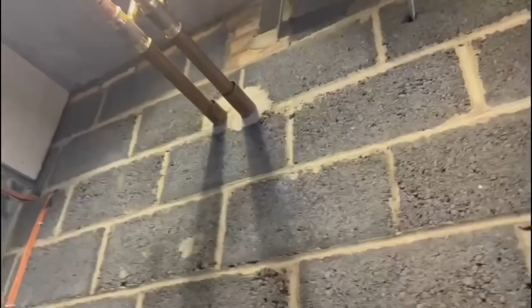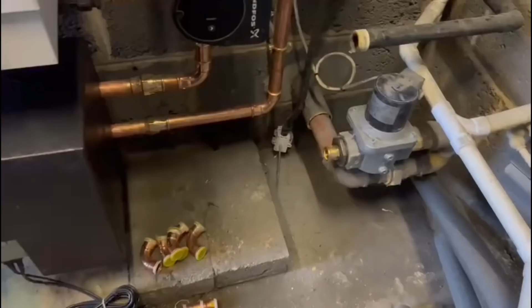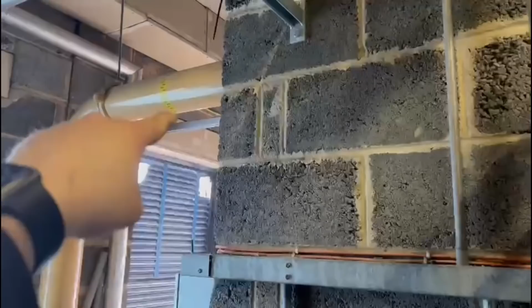Yesterday we got the flow returns complete. As they're connected, AAVs at the highest point, and obviously we'll have to vent on the radiators on the other side. So I think for the moment now, I'm going to concentrate on getting this microfill connected, and I'm going to get this gas done. I don't want to leave an open end for the weekend, so I'm going to get that done. And then I think Monday we'll see us get this flue in. I don't know why, I missed an elbow off the order, so I need one elbow here before we can complete the flue. And then it's electrics.